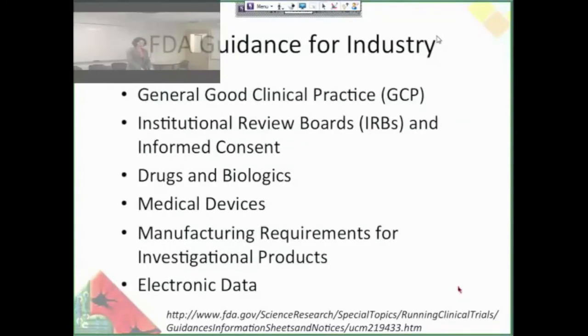Okay, so I mentioned earlier that you should involve the FDA early in your testing so that you don't do any tests that were unnecessary and so that you make sure that you don't have to repeat any tests because you forgot some controls that the FDA is going to require you to have. So the FDA puts out some documents called Guidance for Industry, and these are some of the links that you'll find on the Guidance for Industry page. So there's all sorts of advice that they put out. They're trying to be more transparent.